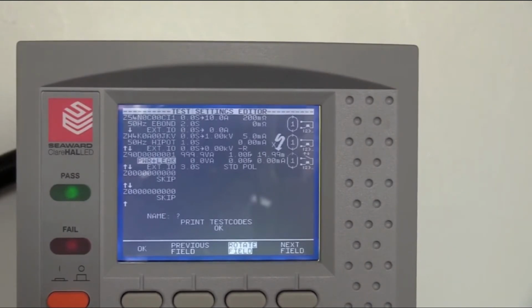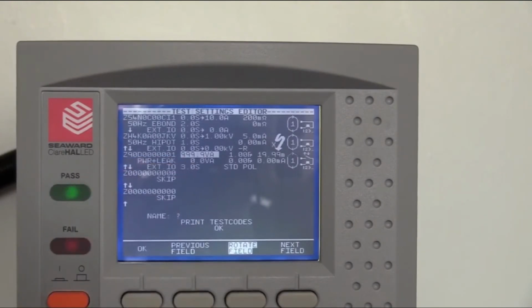So there are a few parameters we need to set for this. The first thing we need to set is our power. Ideally we would know what the nominal power for the unit is at a set voltage, and therefore we could set an upper and lower limit accordingly. At this stage I'm just going to leave these blank. We can define how long we want the product to run for. So if we know there's a longer time for it to build up to its maximum power, we can run that for a longer period of time. Something like a light, for example, pretty much reaches full brightness within a second or two. So these tests can be very quick.